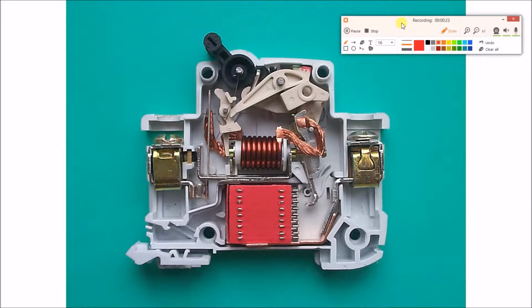Here is the picture of the inside of a circuit breaker. The current begins here, travels here through this path. The red coil in the center is called a solenoid. The solenoid reacts to quick spikes in current and serves as a fast-acting fuse. When this happens, the solenoid will send a plunger through to flick the switch and turn it off, therefore breaking the circuit here.